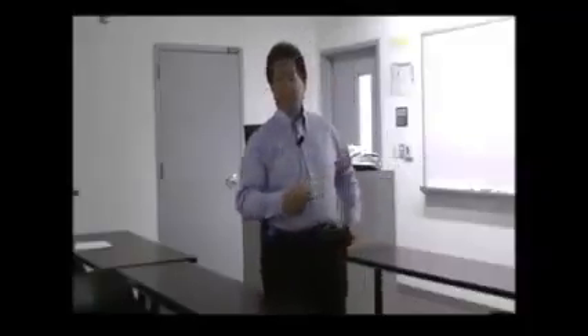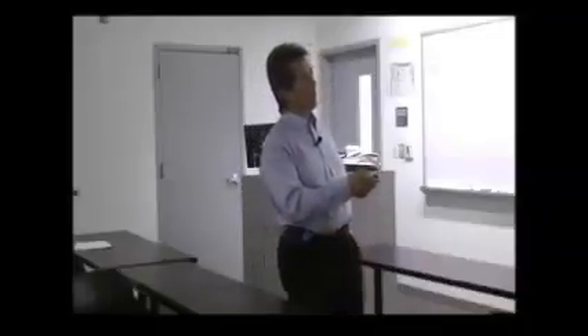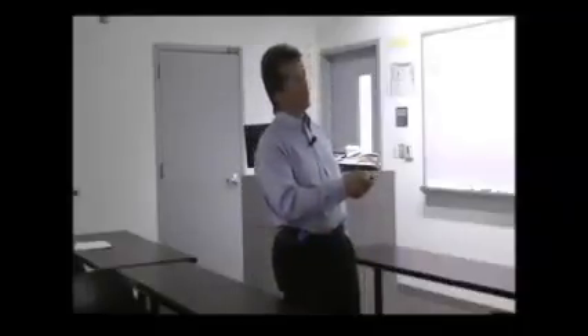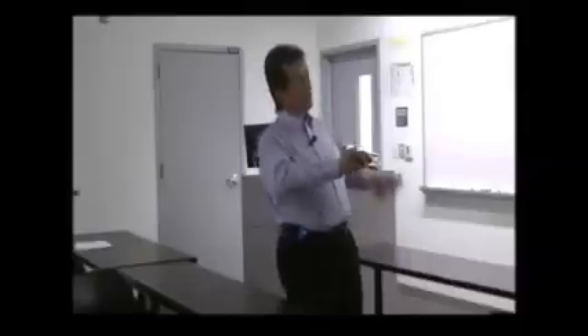Typically, you only see small plumes. So when I drive up to my facility, I don't want to see big plumes. I want to see just a little plume. That tells me that I'm only extracting a minimum amount of heat into the atmosphere for my building. Okay, so everything's balanced and adjusted. So that cascades down, goes back into my suction pump, and starts the process all over. So these are two split systems.